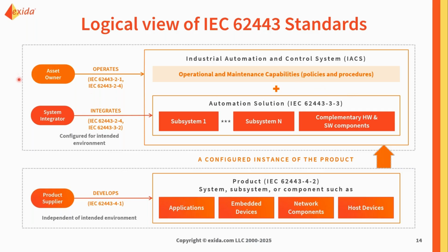One of the nice benefits and differences between NERC CIP and IEC 62443 is that 62443 specifically calls out for each of the different stakeholders what parts of the standard are applicable and what the key controls are. We'll see that for product suppliers—companies building products like RTUs, protection relays, or PLCs used in electric substations—if they comply with 62443, it will make it a lot easier to comply with some of the technical requirements in NERC CIP, which we'll look at later.